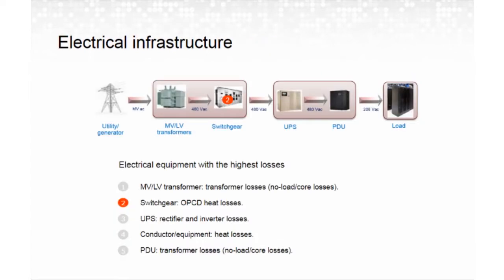Once the service transformer has reduced the system voltage to a usable level, such as typically 480 volts or 208 volts, the distribution equipment that provides overcurrent protection should be evaluated for system losses. While this graphic illustrates switchgear in one location, the losses we cover affect all overcurrent protection equipment.